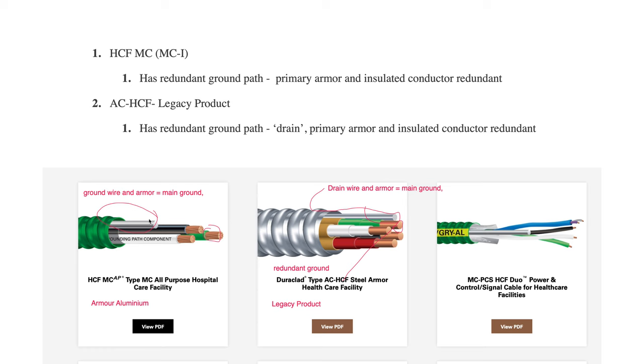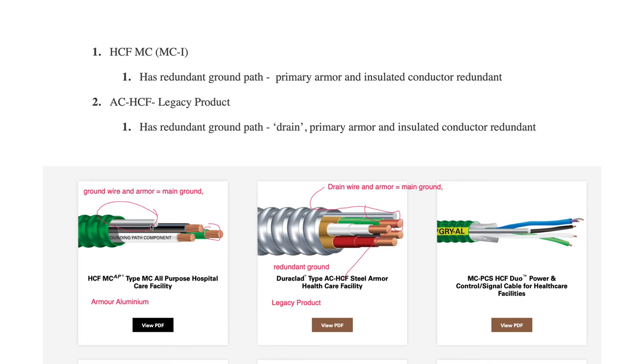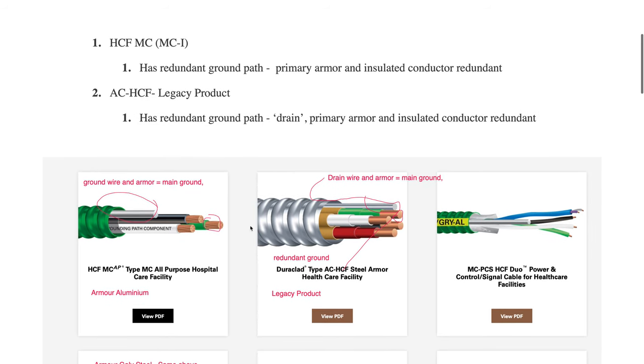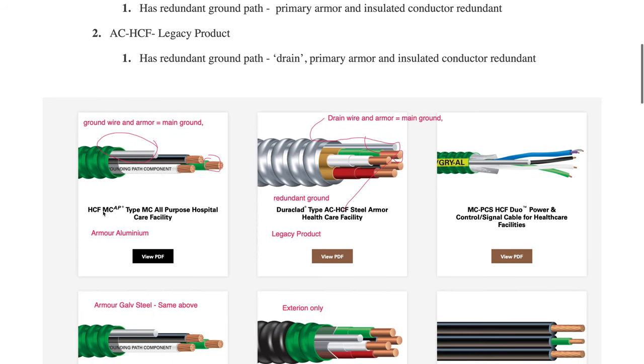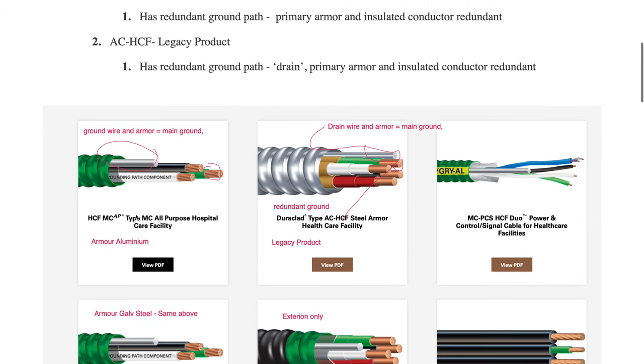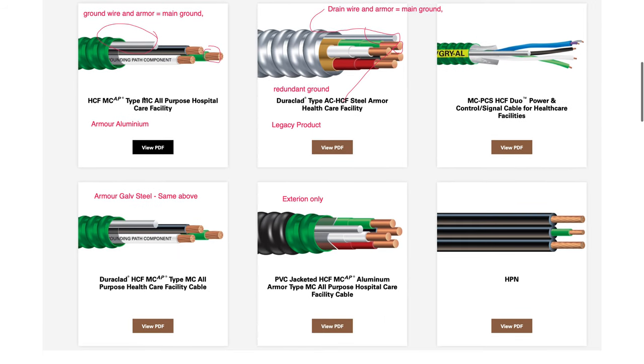The more commonly used wire — and I think it's lower cost because you've reduced the amount of material and also the labor cost of terminations — is called the HCF MC cable. In terms of construction, you still have the two phase conductors, and then you have the primary ground with the armor acting as such, and then the redundant ground is this insulated conductor.